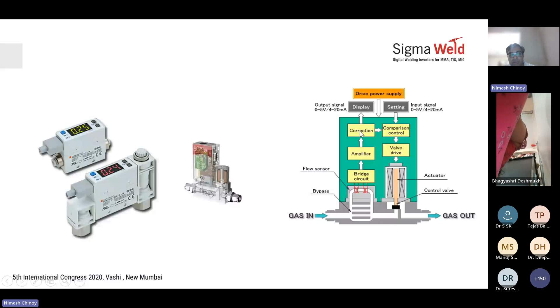Then there is something called the mass flow controller. The mass flow controller has this kind of a configuration where the gas comes in, and you have a bypass which allows you to push the level up. This connects to a bridging circuit, an amplifying and a correction circuit, which then gives you a display of 4 to 20 or 0 to 5 volts. And then you can set how much flow you want through it, and it will do a comparison and open the proportionate valve accordingly. And so that gives you a flow as per what you wanted. So this is called a mass flow controller. It allows you to control the pressure and flow through the system. At the same time, it can capture and collect how much total gas was consumed, and it can share this data with you over 4 to 20 milliamps or over a LAN interface of Ethernet.